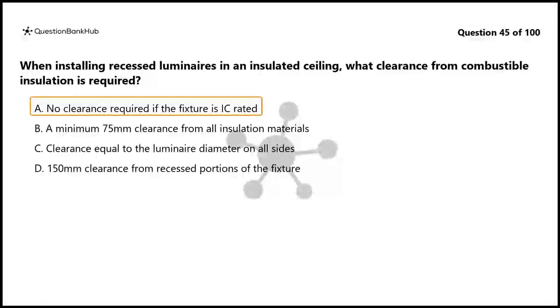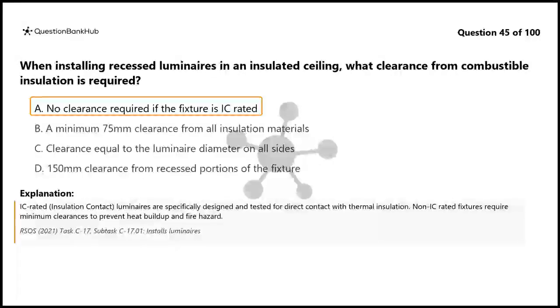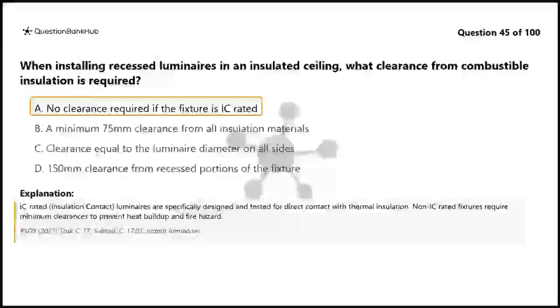The correct answer is A. No clearance required if the fixture is IC rated. IC rated, insulation contact, luminaires are specifically designed and tested for direct contact with thermal insulation. Non-IC rated fixtures require minimum clearances to prevent heat buildup and fire hazard.